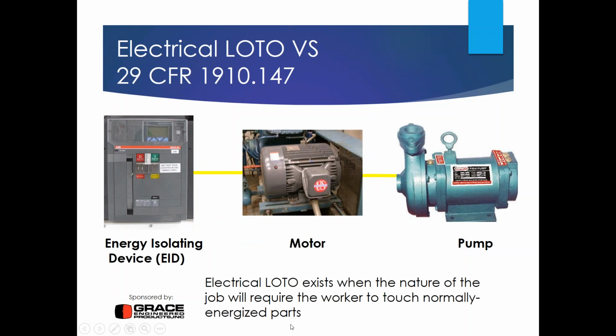Now let's talk about the difference between electrical lockout and mechanical or any other type of lockout, and we'll also talk about the difference between high voltage and low voltage lockout. In this example in the picture, we have an energy isolating device. The term energy isolating device is critically important in lockout because only energy isolating devices can be locked out. You cannot lock out tagout controlling devices like push buttons, toggle switches, safety switches, or emergency stop circuits. You can only lock out tagout an EID.